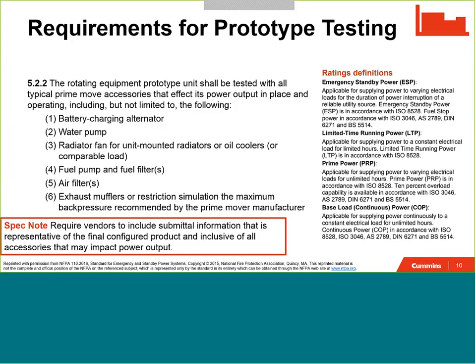What you don't want to see from a generator set manufacturer in their rating definition is a sentence that says something like product rating dependent on configuration. What that tells you is that the product may not have been tested with all the appropriate accessories to yield a prototype that can actually deliver testing results that measure up to what you would expect to see in the field. And so again, this is where I'd recommend that in your specifications, you require vendors to include submittal information that is representative of the final configured product and is inclusive, and the performance data is inclusive of all accessories that may impact the power output or product performance.